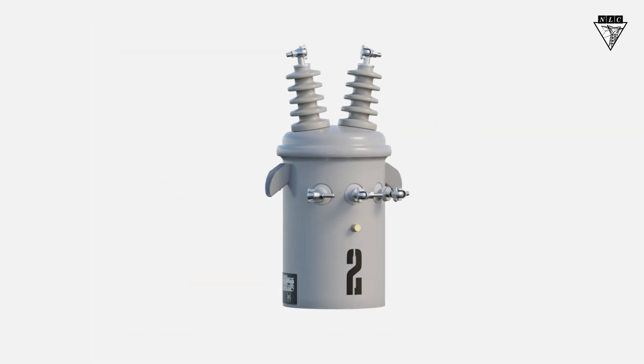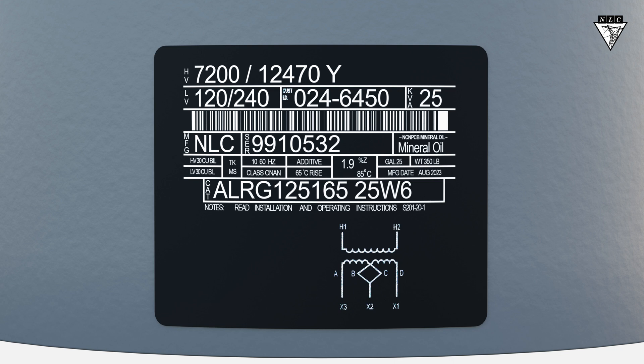We'll start by comparing these three pieces of information to the transformer nameplate. The high voltage rating on the nameplate reads 7200 volts, which matches the phase-to-ground connection on the system voltage. The low voltage on the nameplate is 120/240, which also matches the voltage required by the customer. Lastly, the size of the transformer is 25 kVA, which matches the transformers on the work order.